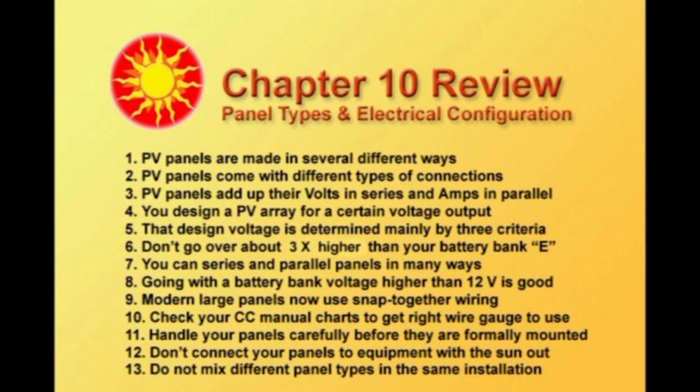That design voltage is determined mainly by 3 criteria. For your panel array, don't go over about 3 times higher than your battery bank's voltage, or E. You can series and parallel panels in many different ways to obtain that design voltage, so the type of panel is not that critical. Going with the battery bank voltage higher than 12 volts is good because it allows you to run smaller wires coming in from the array and have the inverter a little bit further away from your battery bank. Modern large panels now use snap-together wiring, connectored wiring, so it's easier.